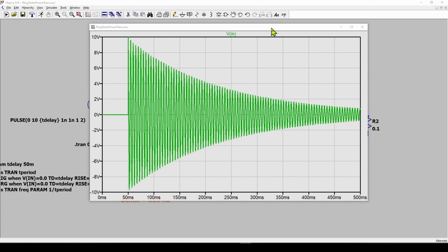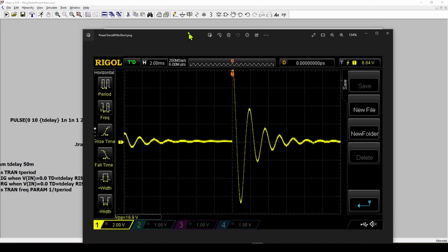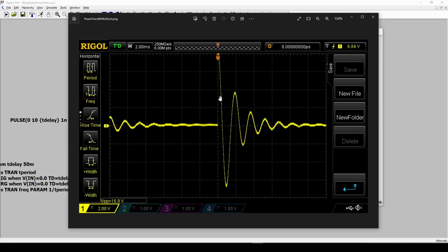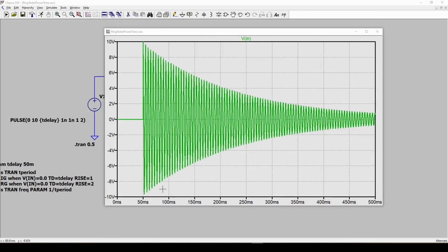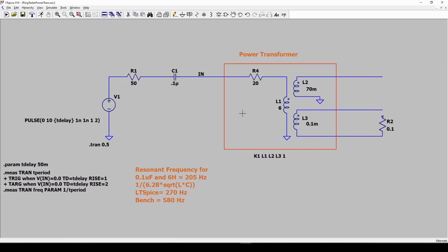Our 60 hertz model isn't working in the real world when we apply, in this case, about a 500 hertz oscillation. And here we're showing 2 milliseconds per division. So it's 2, 4, 6, 8. So maybe around 10 milliseconds, this thing should be damped. Here's 50 milliseconds. It's still ringing a lot. So we need to take a look at our model and see what's going on, why it's not working.